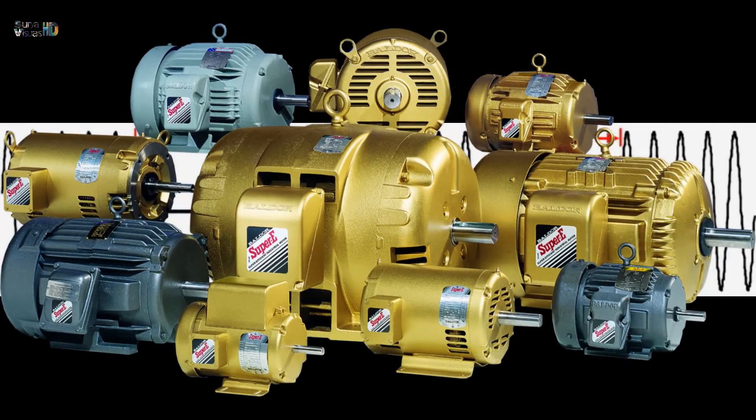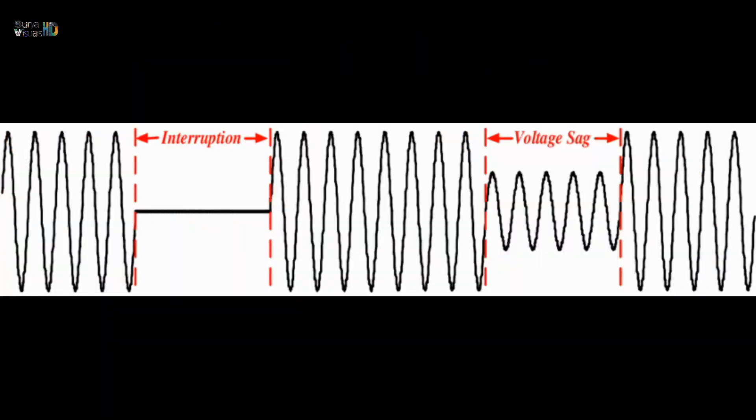Momentary interruptions, typically no more than 2 to 5 seconds, cause a complete loss of voltage and are a common result of the actions taken by utilities to clear transient faults on their systems. Sustained interruptions of longer than one minute are generally due to permanent faults.